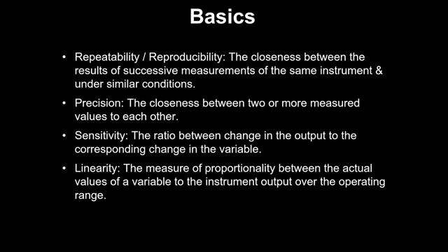Then sensitivity of the instrument, that is how quickly or how effectively the changes get recorded. If there is a small change, suppose the temperature goes up from 100 degrees to 120 degrees in 1 minute, how much time will our instrument take to record a similar change? Can it show instantaneously? No, no instrument will show instantaneously. It is going to take some time. Now that time lag would depend on the sensitivity. The more sensitive the instrument, the quicker it will show it. The less sensitive the instrument, it will take slightly more time. So one needs to take care of this, especially when you are taking higher temperature readings, or doing humidity or such kind of readings. Humidity or wet bulb temperature readings normally take more time than simple temperature. And when you want more accuracy, you probably need to be more careful about the sensitivity of the instrument, because the audit team has a tendency of not waiting long enough to see the reading stabilize.